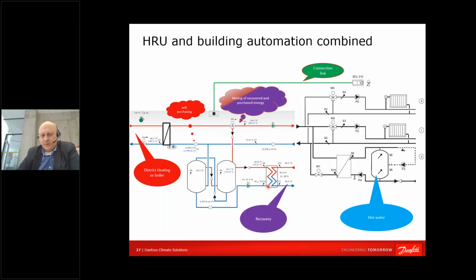To repeat, quite simple: charging tanks, sending to the building. If the building requires extra effort and tells us to change something, then we can either invite the district heating utility, or we can ask for more energy from the cooling rack. Quite simple. Okay, here I have a balancing valve, which we are using just to prevent too large a flow, because it's quite difficult for us to align the pump and heat exchanger in the plants.